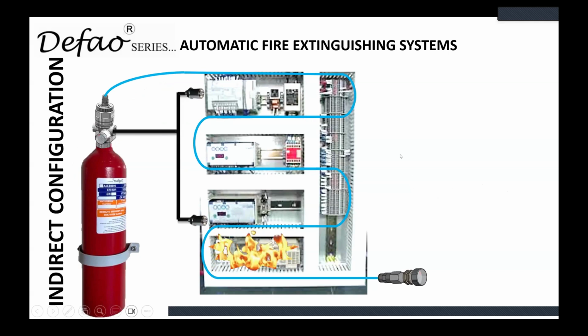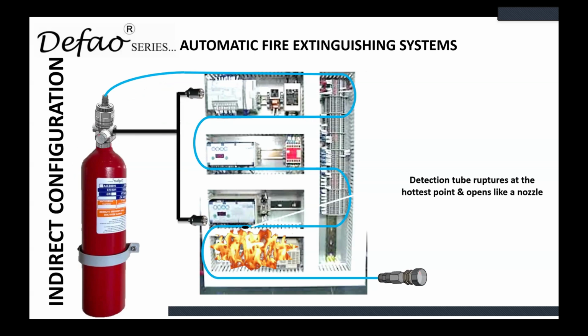So here, again, in case of fire, the hottest part ruptures and opens like a nozzle. Here, the gas is discharged through the pipes and through the nozzle arrangement rather than the tube. So here, the tube acts as the fire detector and the tubing system acts as the extinguishing system. So this is the indirect configuration.